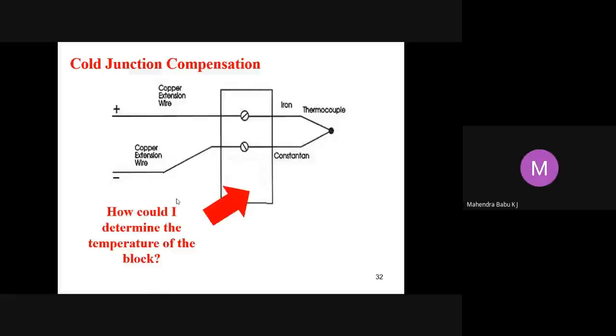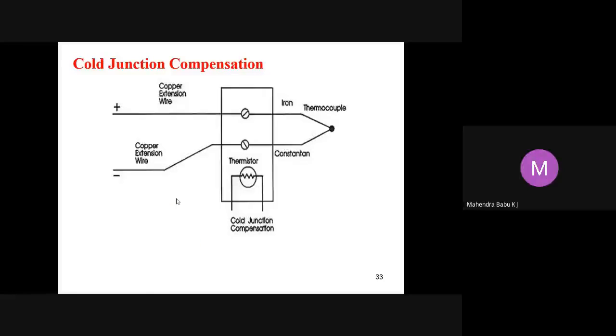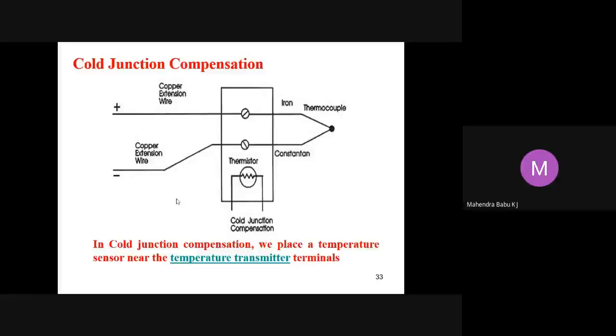Then you have to make use of cold junction compensation. Compensation is provided for the cold junction. How does it work? In cold junction compensation, we place a temperature sensor near the temperature transmitter terminal. Near the temperature transmitter, some temperature sensors are provided in a cold junction compensation, or we call it cold junction compensation.